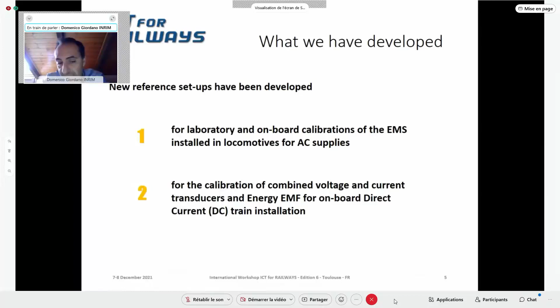Here you can see the structure for calibration of the energy measurement function for AC, both 16.7 Hz and 50 Hz systems. The setup is constituted by two voltage and current amplifiers. Signals at low amplitude are amplified by voltage and current instrument transformers, so we are able to apply both voltage and current at the same time.